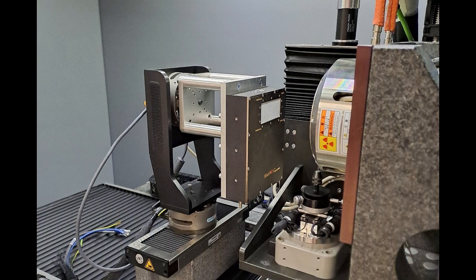We have mentioned that there is a fundamental difference because we are using photon counting. How do we understand photon counting compared to traditional flat panels? If you have a scintillator detector, for example, it is integrating the energy over the range which you're using. And for dense objects, you have a high energy, so this is even more pronounced.